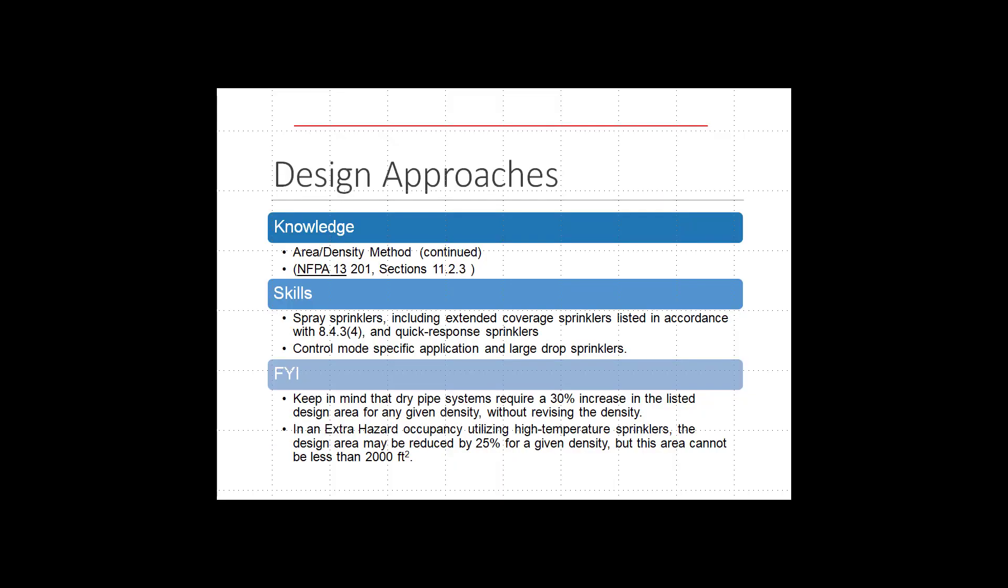In an extra hazard occupancy utilizing high temperature sprinklers, the design area may be reduced by 25% for a given density, but this area cannot be less than 2,000 square feet.